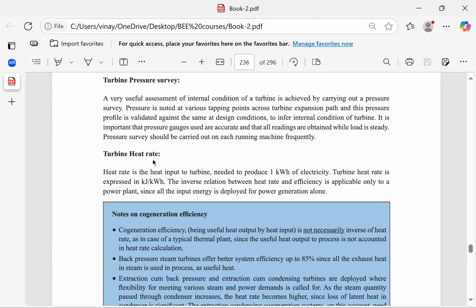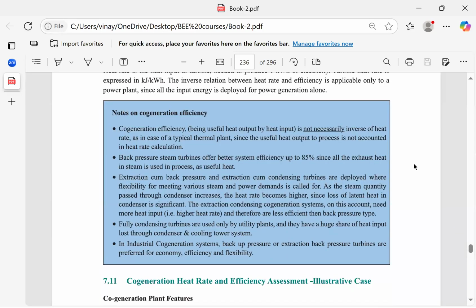Then turbine heat rate - same meaning. To produce 1 kWh of electricity, how much heat input is required to a turbine? It is expressed in kilojoules or kilocalories per kWh. The inverse relation between heat rate and efficiency is applicable only to a power plant, meaning when the turbine is fully condensing and used only for electricity generation.